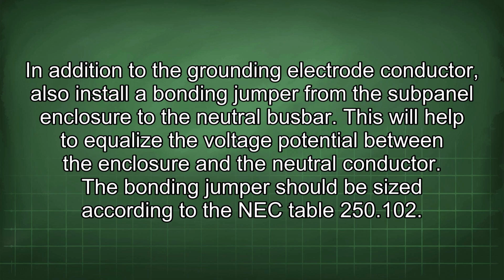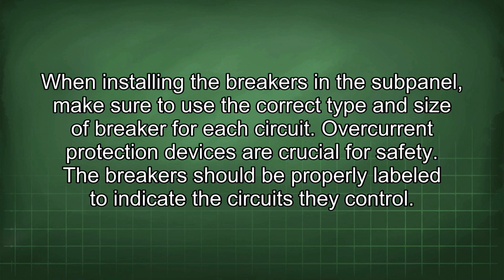This will help to equalize the voltage potential between the enclosure and the neutral conductor. The bonding jumper should be sized according to the NEC Table 250.102. When installing the breakers in the subpanel, make sure to use the correct type and size of breaker for each circuit. Overcurrent protection devices are crucial for safety.